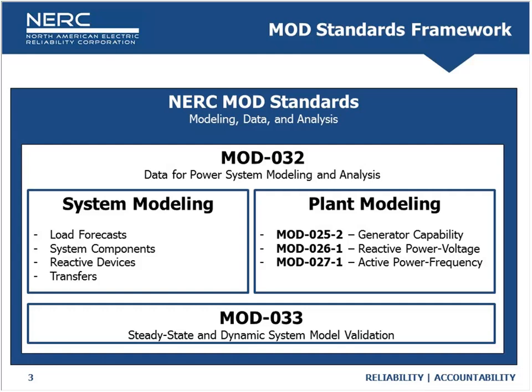MOD-26 and MOD-27 are specifically where we'll be focusing in this conversation. MOD-33 goes hand-in-hand with MOD-32; it's the system-wide model validation that the planning coordinators perform. When a large grid disturbance happens, they'll try to recreate it using their interconnection-wide models. MOD-26 and MOD-27 are more from a component or individual plant perspective, while MOD-33 is a validation piece from the system's perspective.